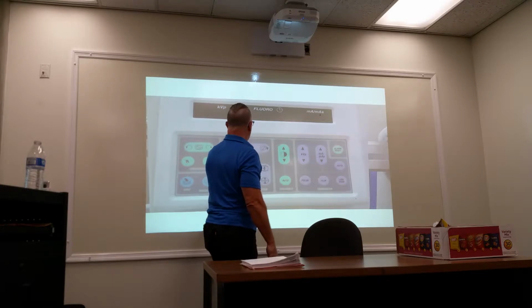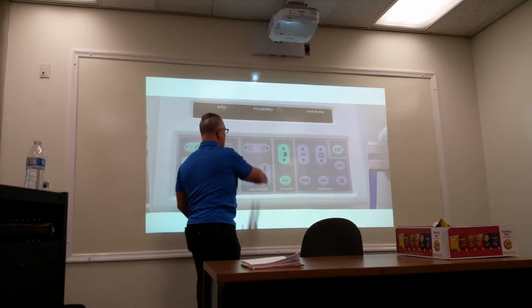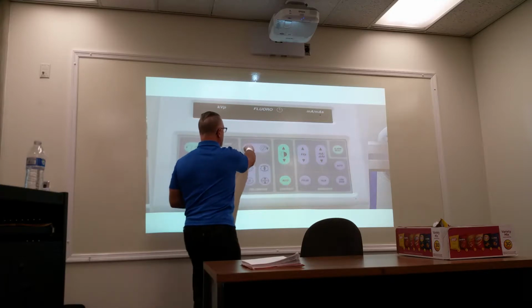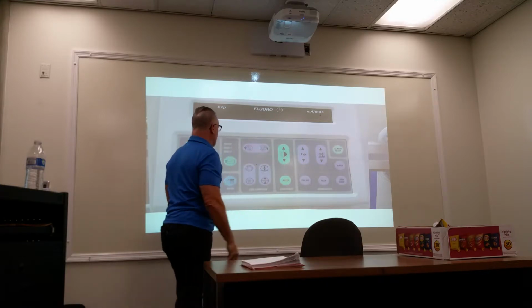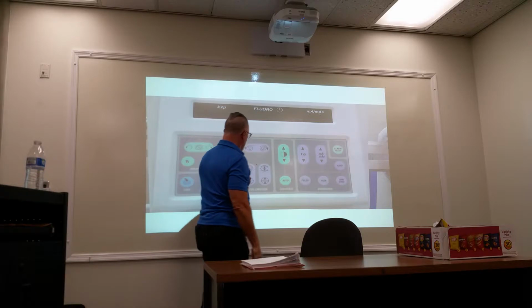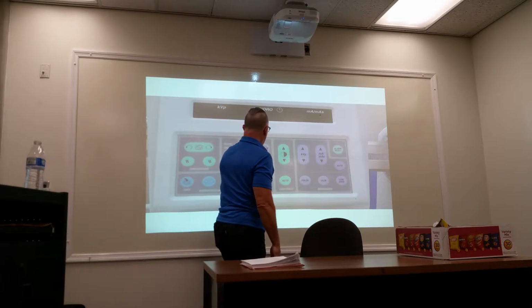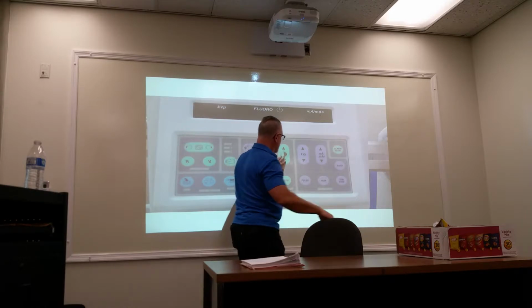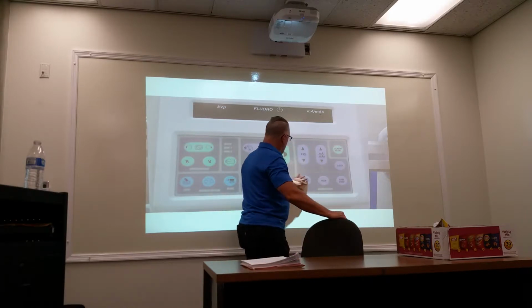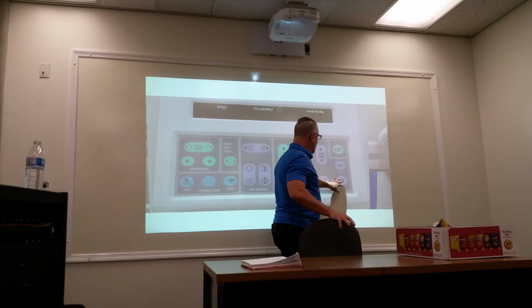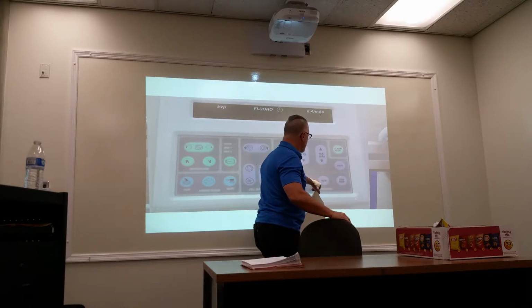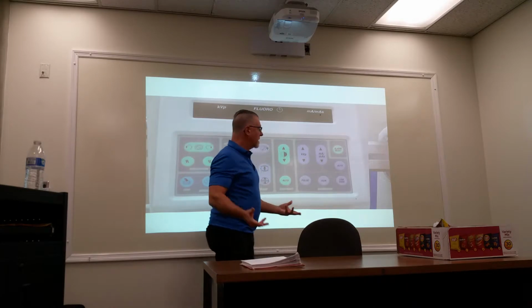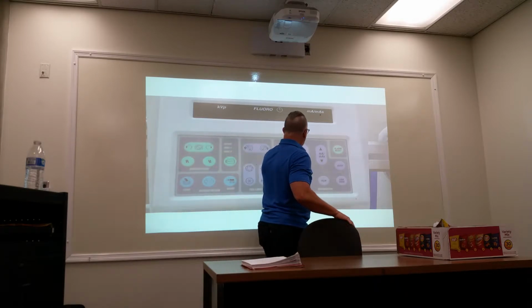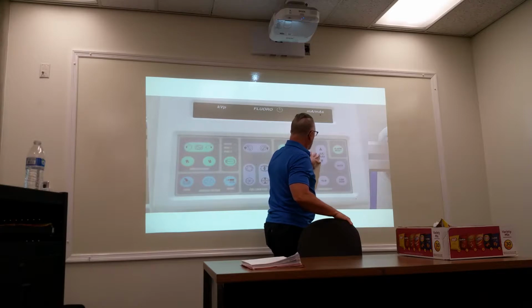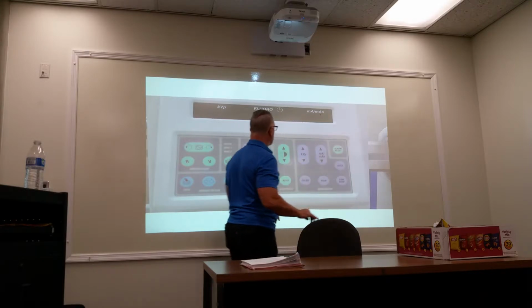This is your blade collimation. You can actually rotate the blades, which is kind of interesting. This is your aperture control, collimation in and out. Auto contrast, or you can change contrast yourself. Now you've got pulse mode, you've got low dose, you have film. Film means you're going to take a, in this case, a CR image. kVp control, mAs, and this is your alarm reset.